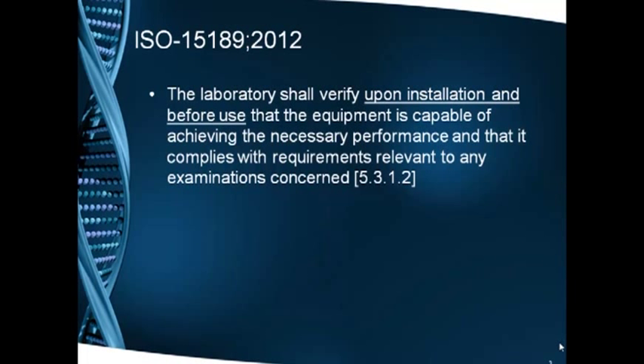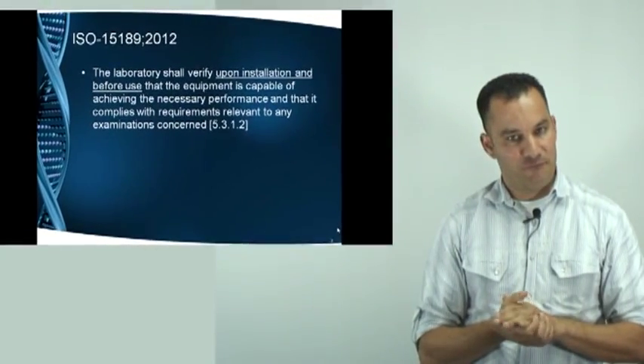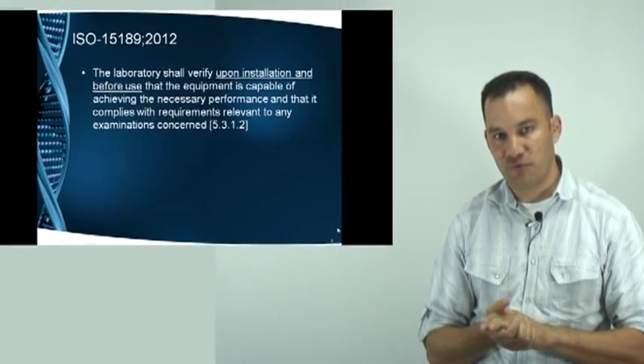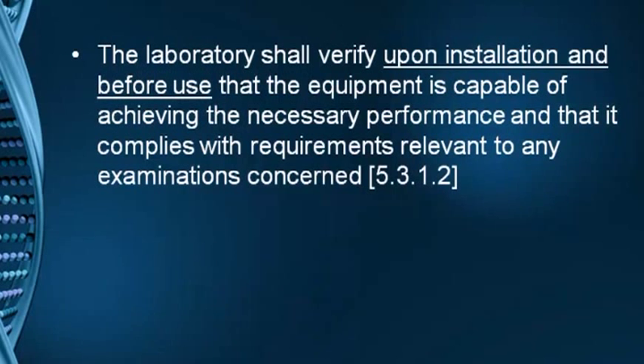Let us start by examining ISO 15189, the 2012 edition, which is the latest one and is currently active. Chapter 5, paragraph 3.1.2 states that the laboratory shall verify upon installation and before use that the equipment is capable of achieving the necessary performance and that it complies with the requirements relevant to any examinations concerned.